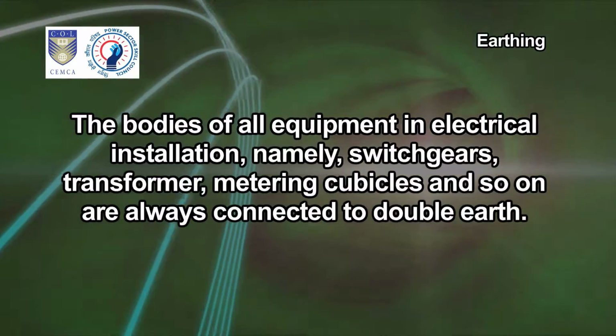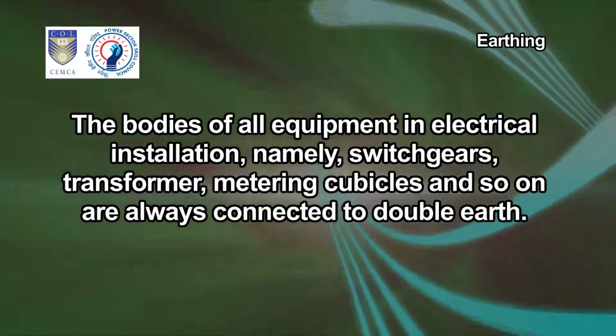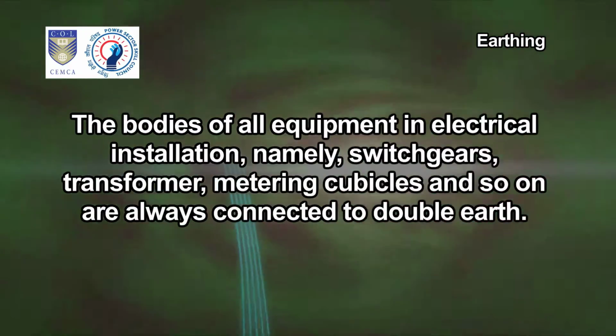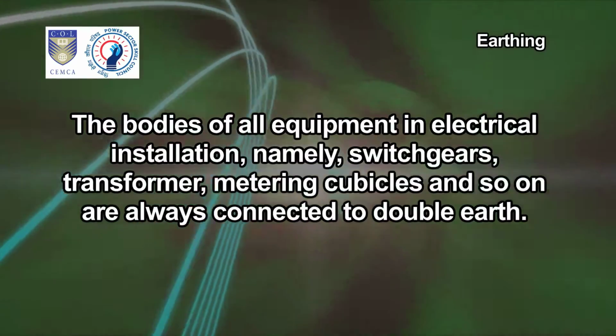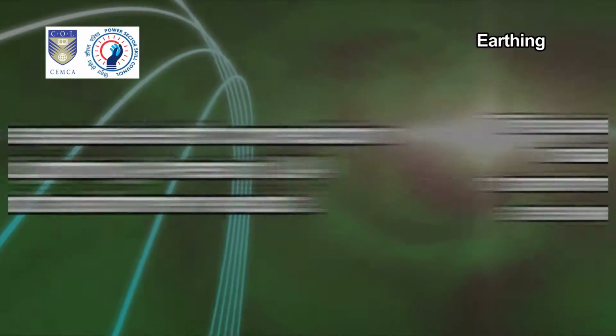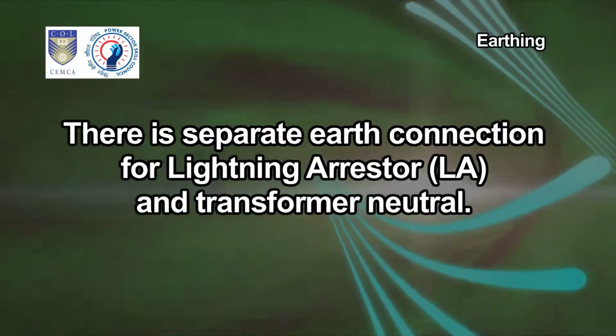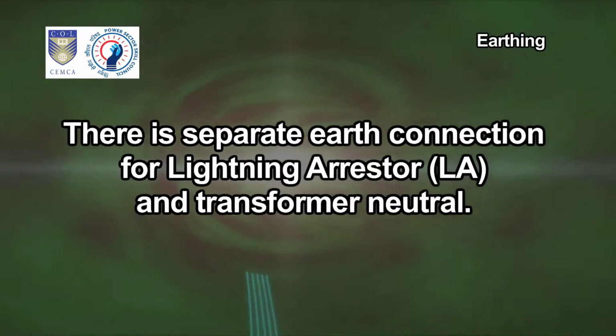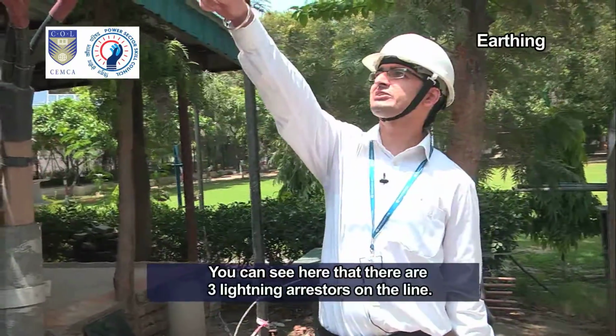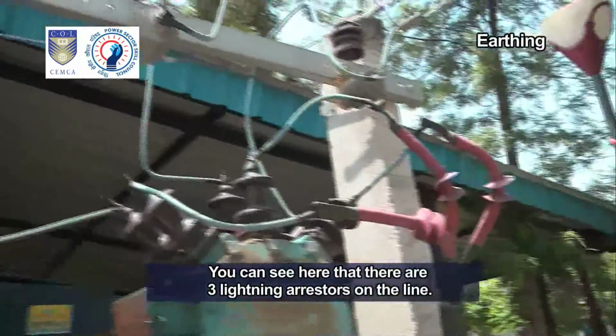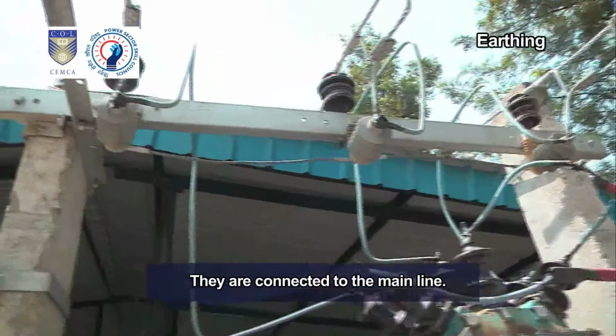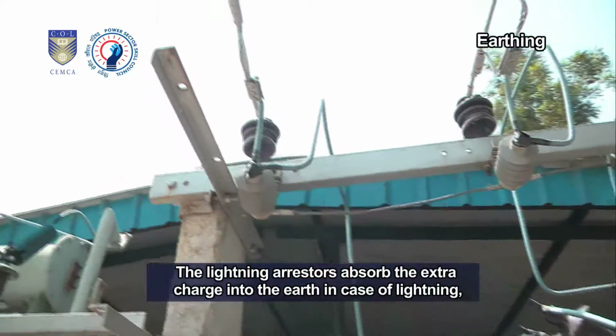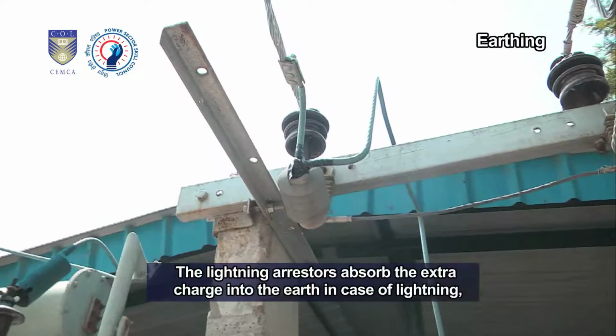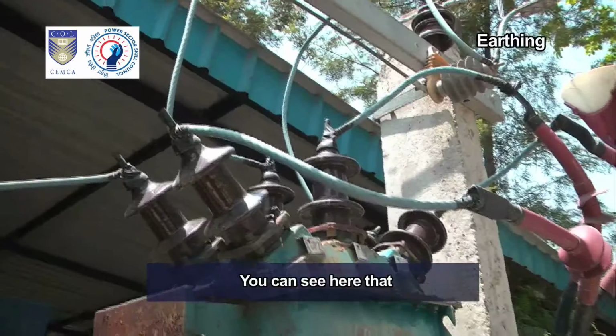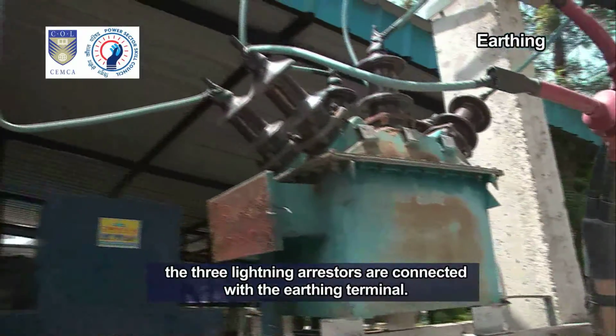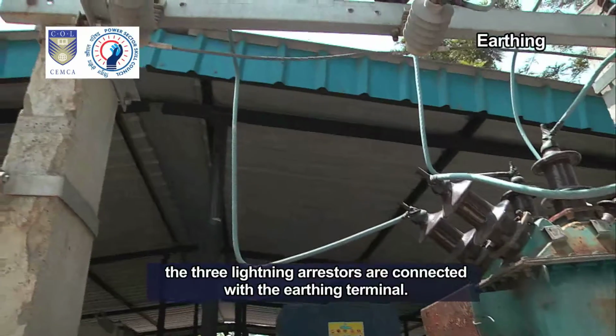The bodies of all equipment in electrical installation, namely switch gears, transformer, metering cubicles and so on, are always connected to double earth. There is separate earth connection for lightning arrestor LA and transformer neutral. You can see here that there are 3 lightning arresters on the line. They are connected to the main line. The lightning arresters absorb the extra charge into the earth in case of lightning and save the equipment. You can see here that the 3 lightning arresters are connected with the earthing terminal.